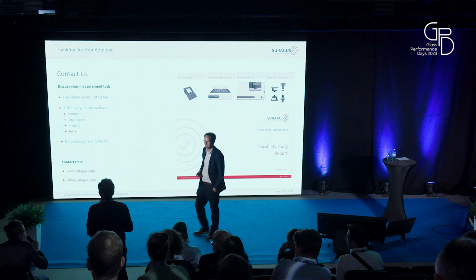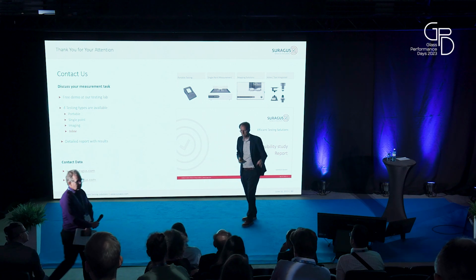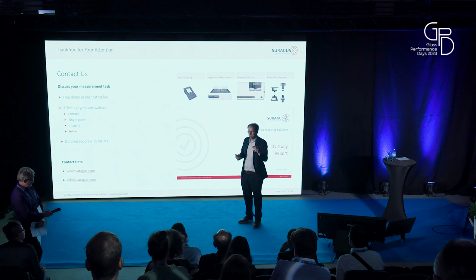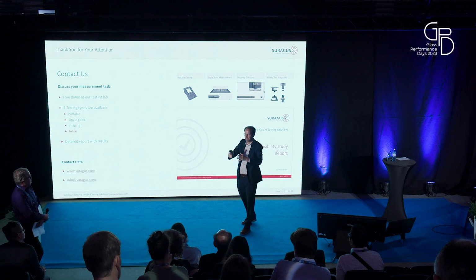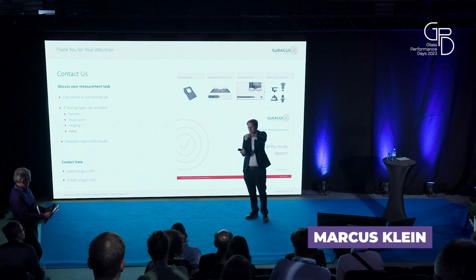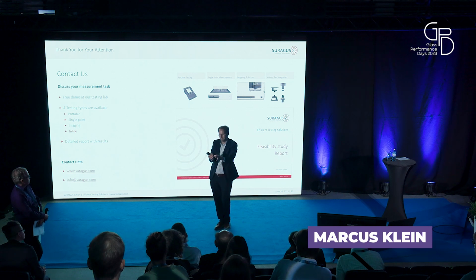What is the measurement spot size of the eddy probe? Also a good question. So technically, we have spot sizes from 1 millimeter to 100 millimeter. The smallest coil that we use is 875 microns wide. But you have a very small field. It doesn't go far away. So in the glass applications where we typically have large distances, sometimes like 40 millimeters, when we have thick glass coming through, then of course the measurement field, we have the rule of thumb 2 times gap. So if I have a 20 millimeter gap, then we have a 40 millimeter measurement spot.